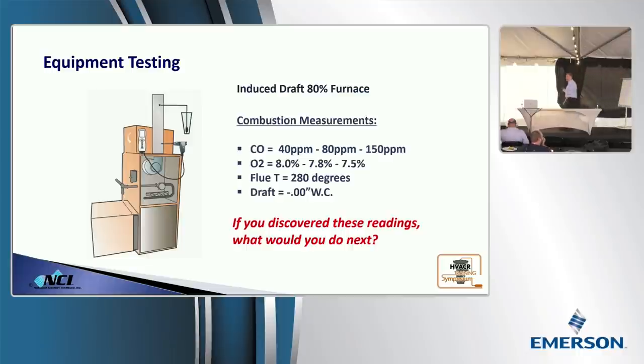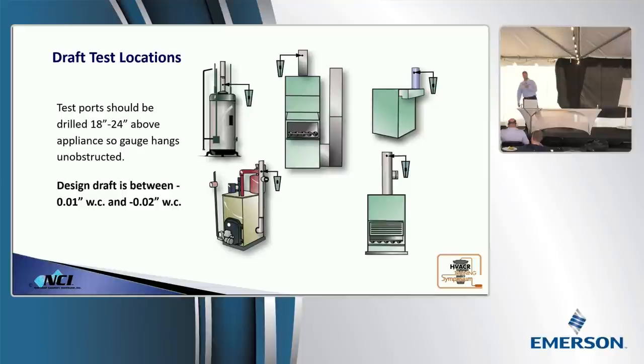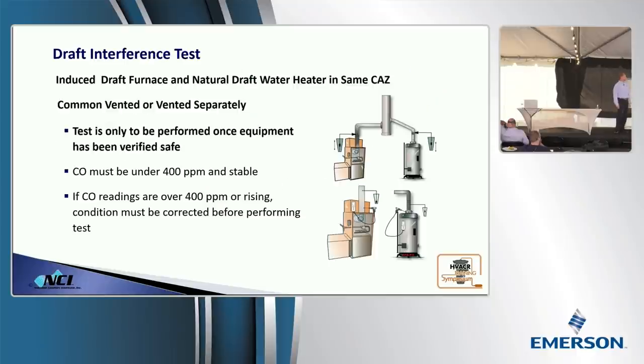Now, as we start to go through the test results, we now add draft to this. We already took the reading previously. Draft is going to be 18 to 24 inches above the draft hood. And that's where you're looking for that 0.01 to 0.02 inches of water column range. If you're within that and you've got stable CO less than 100 parts per million and stable oxygen between 6 to 9%, you're good to go. But if you see rising CO, falling oxygen with low draft, you got a problem.